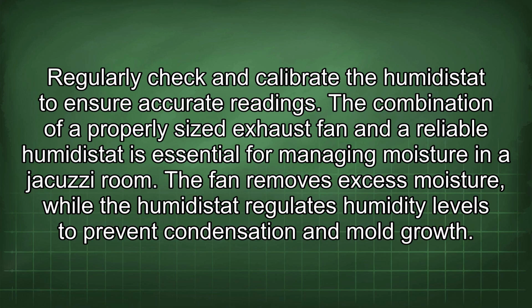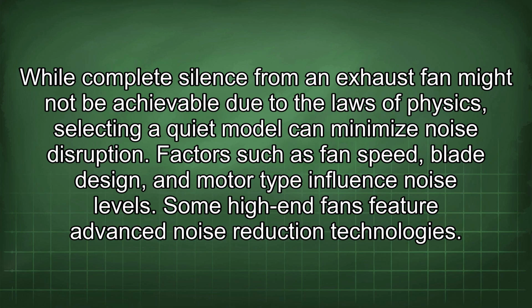Regularly check and calibrate the humidistat to ensure accurate readings. The combination of a properly sized exhaust fan and a reliable humidistat is essential for managing moisture in a jacuzzi room. The fan removes excess moisture, while the humidistat regulates humidity levels to prevent condensation and mold growth. While complete silence from an exhaust fan might not be achievable due to the laws of physics, selecting a quiet model can minimize noise disruption. Factors such as fan speed, blade design, and motor type influence noise levels. Some high-end fans feature advanced noise reduction technologies.